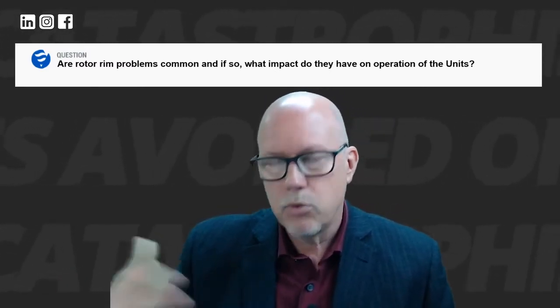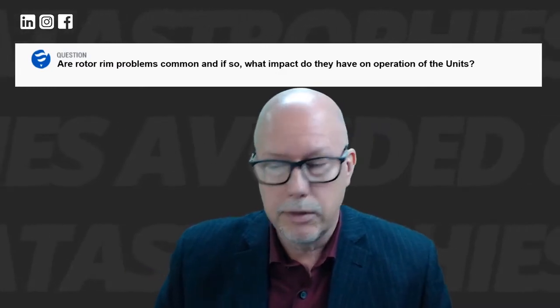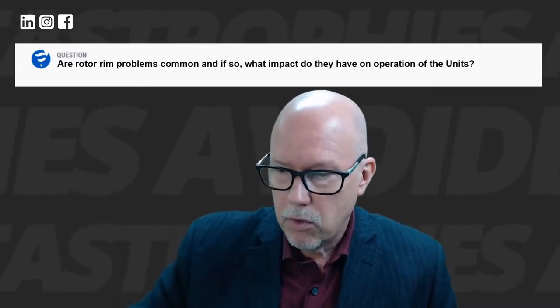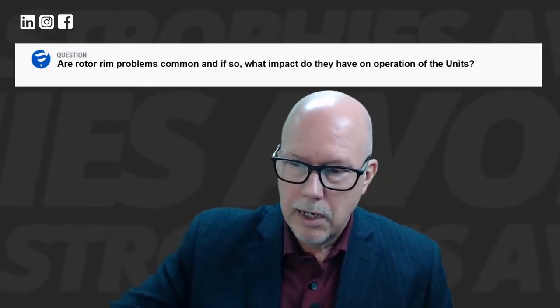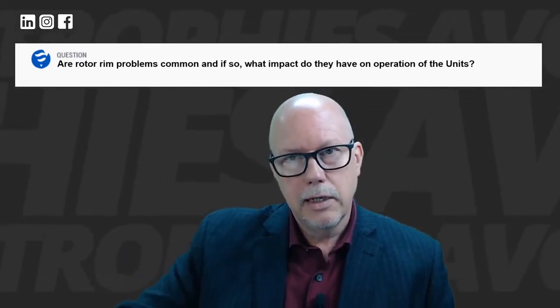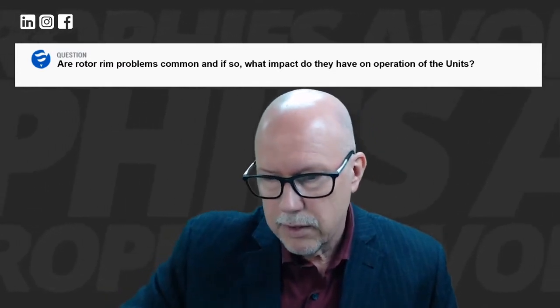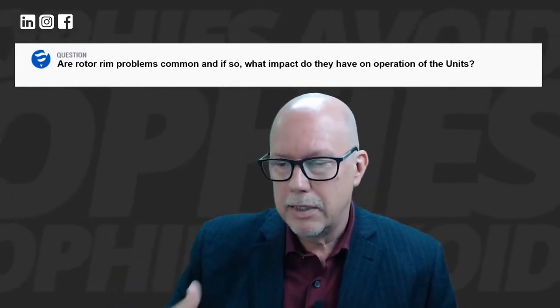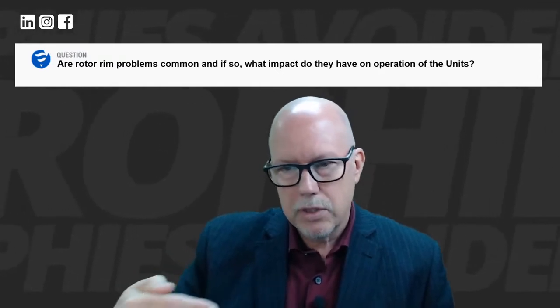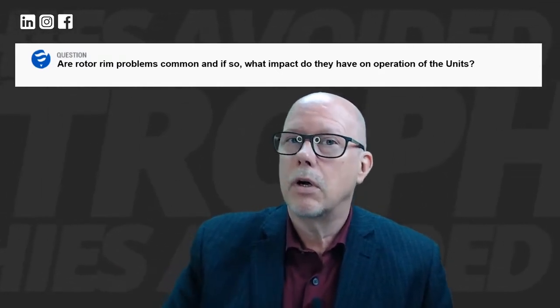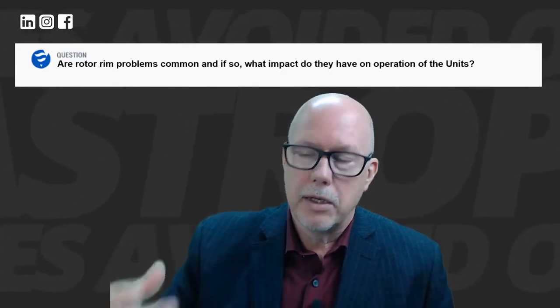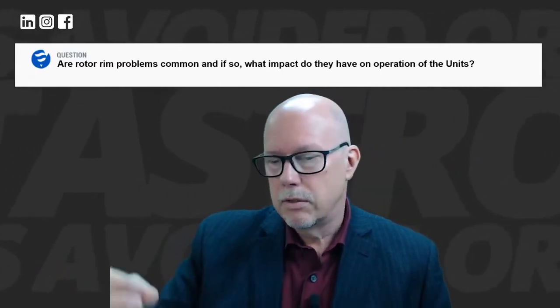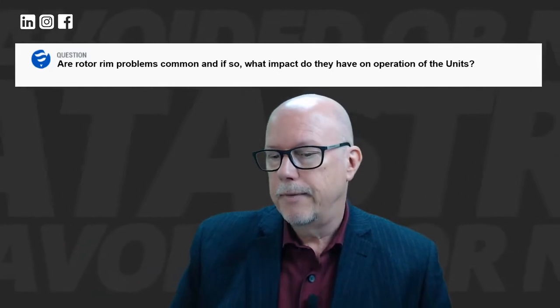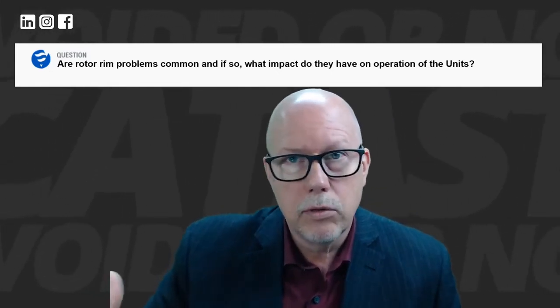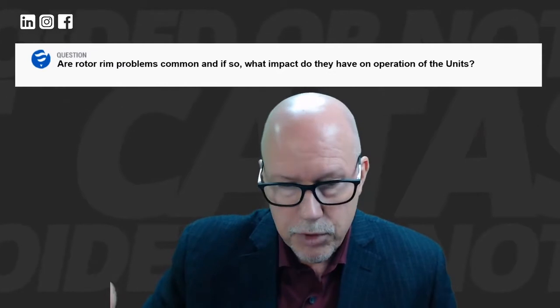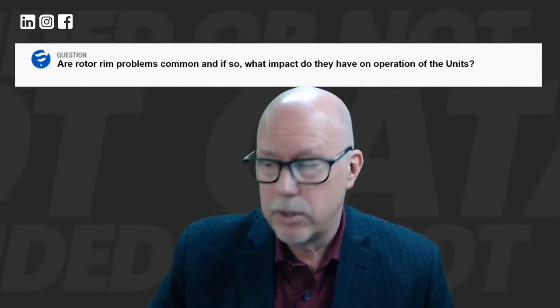Now, that's the best way to create wear and tear on a unit. You subject the core and the bars to high flux intensity, slightly less flux intensity, high flux intensity, slightly less flux intensity at each rotation. And that will produce a stress that will cause eventually possible stator bar vibration, wedge loosening. You might have some core looseness from the frame if it's subjected to this variation for long periods of time.